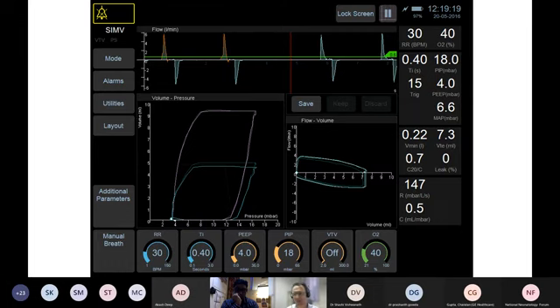In addition to that, you'll see all these measurements down here. We can start measuring the tidal volume that's delivered to the patient on a breath by breath basis. Or over a period of a minute, we can measure the minute ventilation. So it's giving us flow. Flow can allow us to derive the volume that's delivered to the patient. So we can really start to tune ventilation to becoming lung friendly and lung protective through control of these tidal volumes.